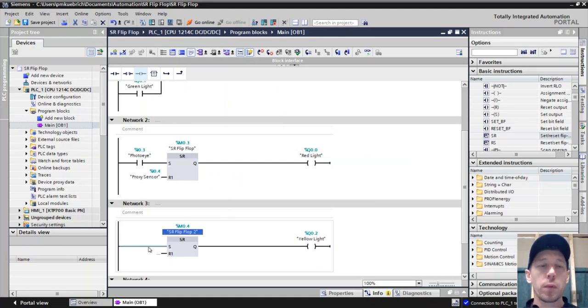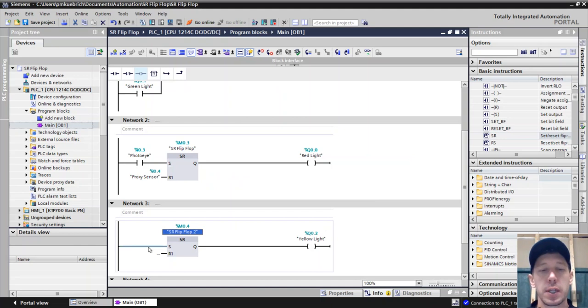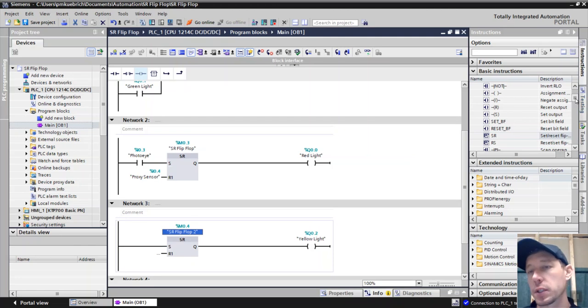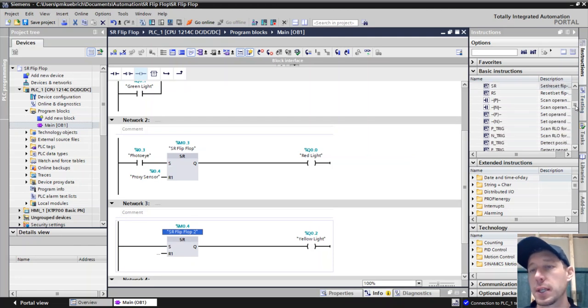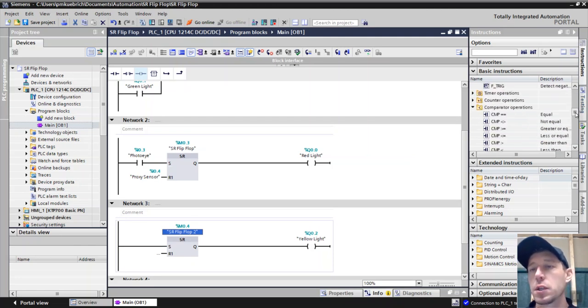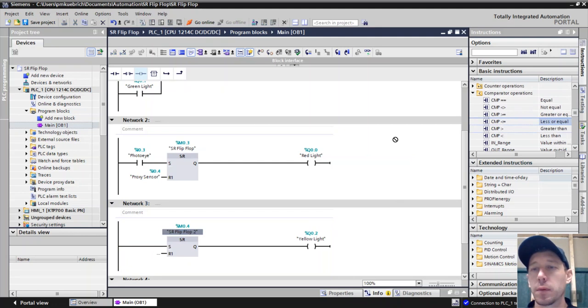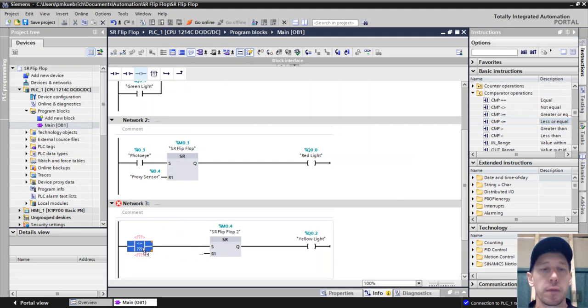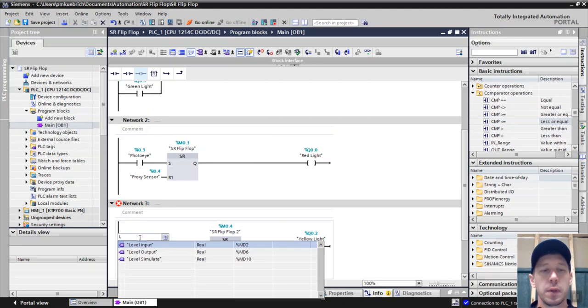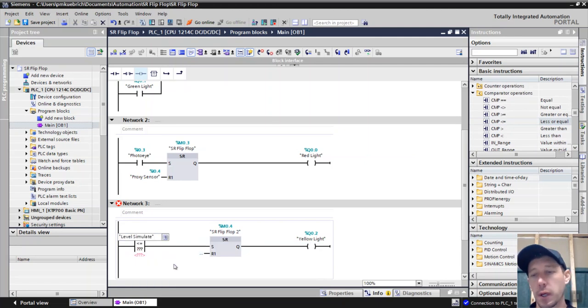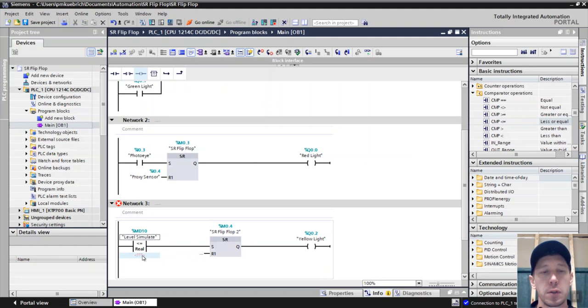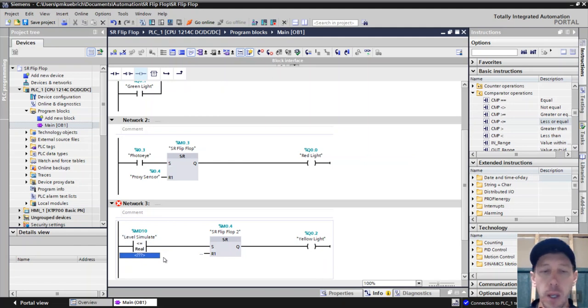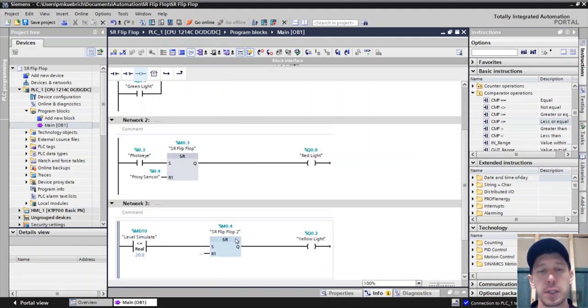Now what do we want to have this set as? We want to use this to turn on a pump to fill up a tank. So we want to turn the pump on anytime we're less than twenty percent, anytime the tank is empty. So what I'm going to do is find a comparator less than or equal to and bring that in for my set. And we will just call this simulated level or level simulate. So I'm not connected to an actual level transmitter today. I'll be able to put a number in for that and when we're less than twenty percent of that tank level, then we'll set our flip-flop and turn it on.